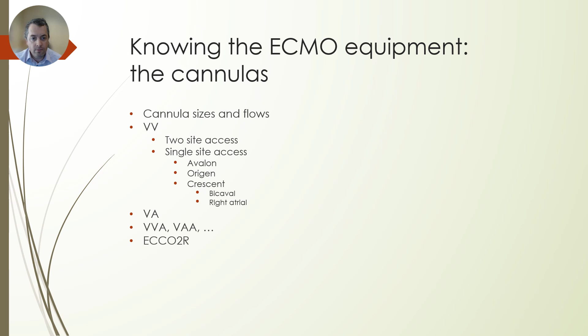You can see that there's a nonlinear relationship between the pressure drop and flow across a cannula, and the shape of that curve is different and more steep for the smaller cannulas. For example, for a 13 French cannula to go from a flow rate of a half liter per minute to 1 liter per minute would take the pressure drop from 100 to almost 300, whereas for the larger cannula to go a similar rate from 0.5 to 1, you see almost negligible pressure changes. And this can have a great effect. Almost always want to have the biggest cannula size that the vessels will tolerate.